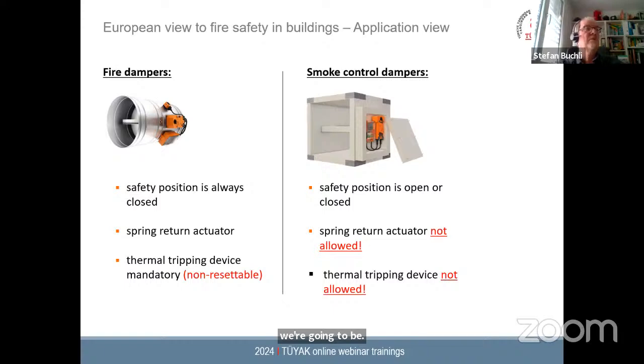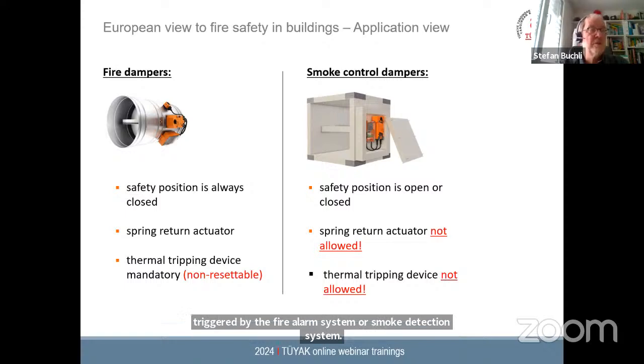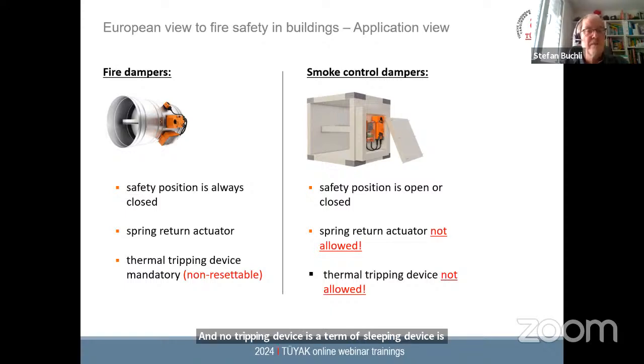Then on the smoke control dampers, the safety position is open or closed, so two safety positions. That's the reason why no spring return actuators are allowed. And the smoke control system is always triggered by the fire alarm system or smoke detection system. No thermal tripping device is allowed on the dampers. This is also coming from the standard. It doesn't make sense, because you detect the smoke and start the smoke control system very early, on detection of the smoke.